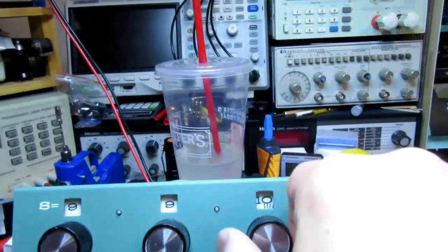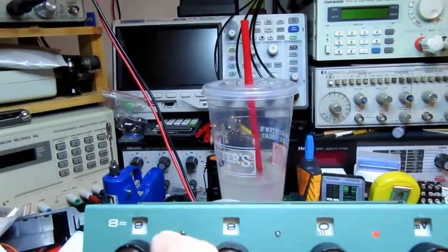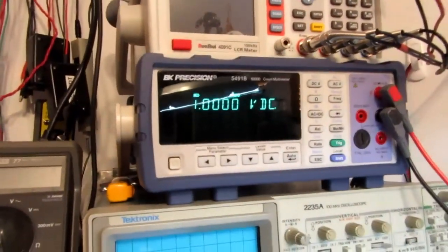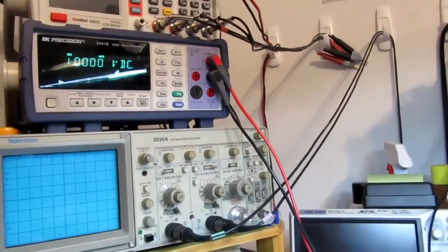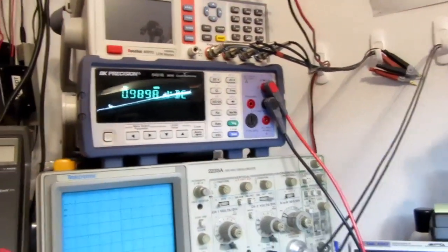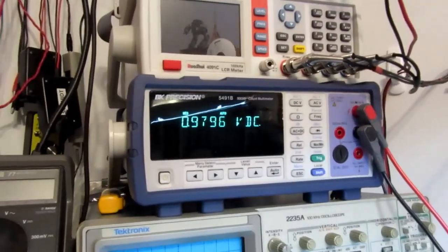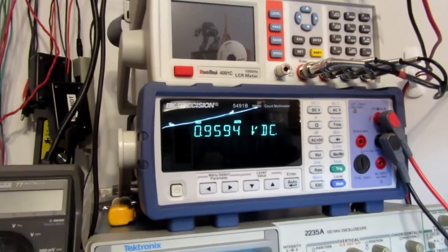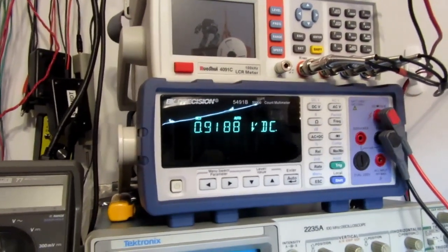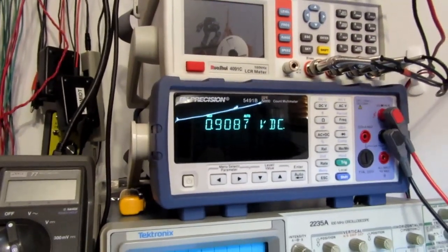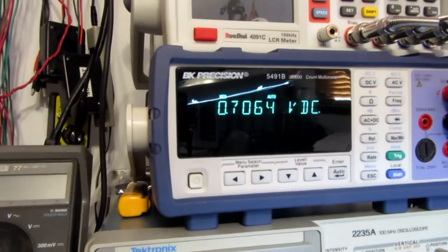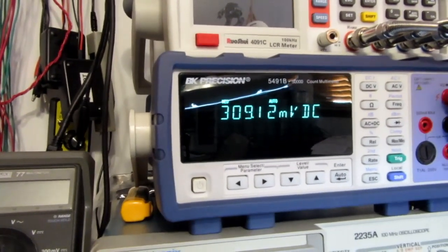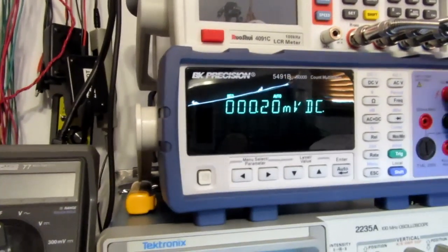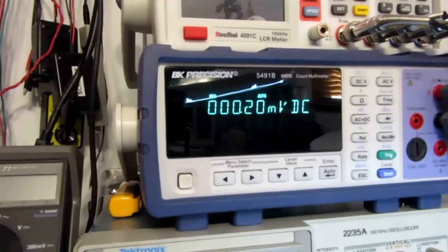I'm going to take the knob down to 9, so now it should be 990 millivolts, and it's still showing me basically the same thing. If I go to 8 here, and I can select it down, so now it should be about 900 millivolts. And if I take that down, 8, 7, 6, 5, 4, 3, 2, 100 millivolts, 100 millivolts, 0. Still with that quiescent amount over there in the least significant digit.